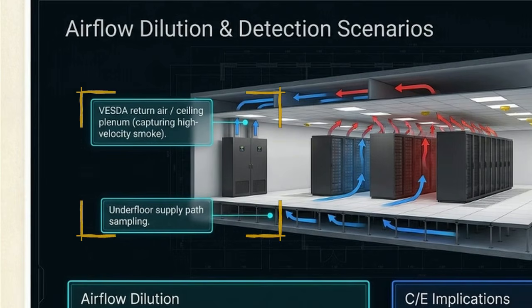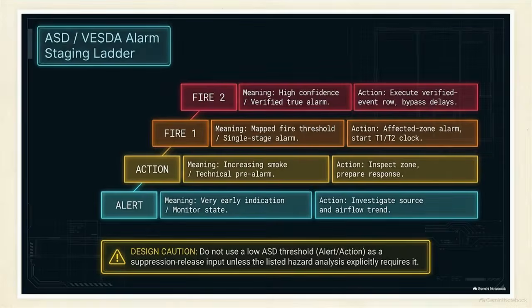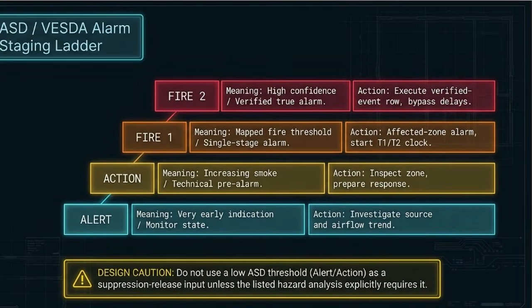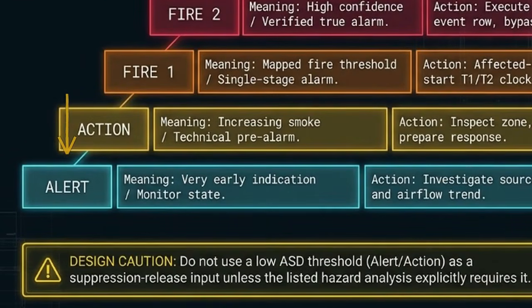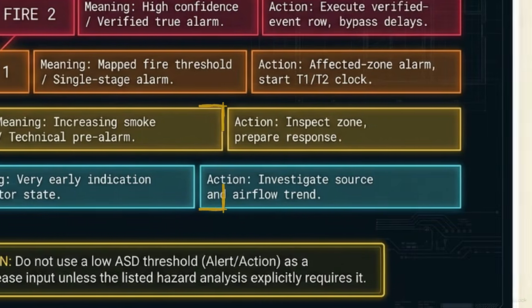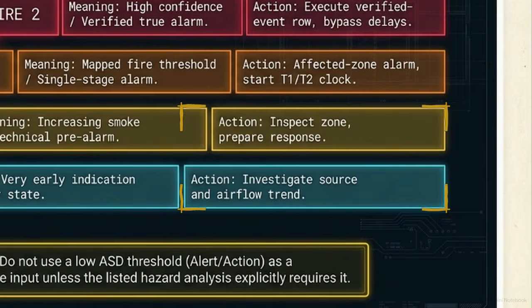Aspirating smoke detectors continuously sample the air by drawing it from underfloor supply paths and high-velocity return air plenums. This staging ladder breaks down how those aspirating smoke detectors, or ASDs, classify the diluted smoke. The system climbs through 4 tiers, moving from a very early alert monitor state up to a Fire 2 verified true alarm. Because of severe dilution, the early alert and action states are strictly technical investigation states. They prompt personnel to inspect the zone, but they are not evacuation triggers.